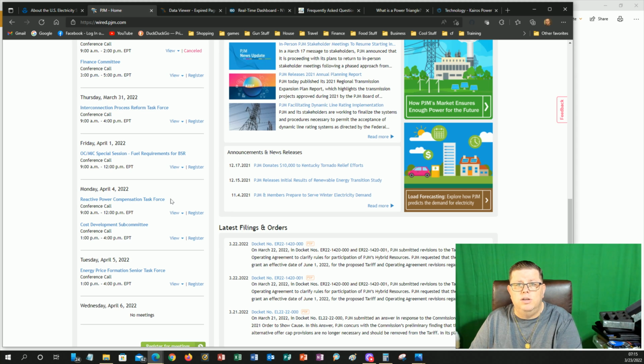So other devices that aren't necessarily generators, you have things called synchronous condensers, which don't provide power as megawatts but provide reactive power only. Older generators that have been decommissioned and are no longer viable from a megawatt perspective can be converted into synchronous condensers to give voltage support in weak areas. There are also devices called SVCs, static var compensators, which use inductors and capacitors on solid state equipment to provide reactive support in key areas that are historically bad for voltage.